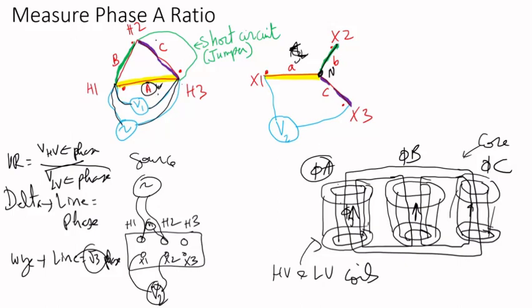Then, because I have phase A here, I can short from H2 to H3. By shorting it, basically as if it doesn't exist, the flux in phase C will be eliminated. If I look at phase C, there will be no flux, as if it's shorted. So I create a virtual neutral, because no flux will be induced since I shorted phase C on the high side. So phase C on the low side will also be as if it was shorted, and no flux will be induced.